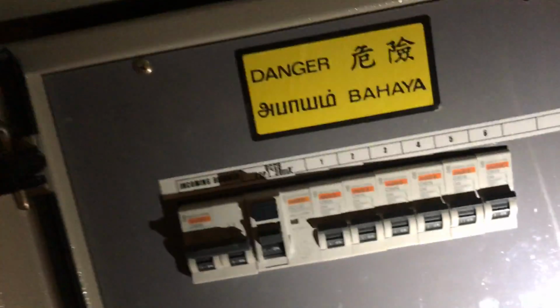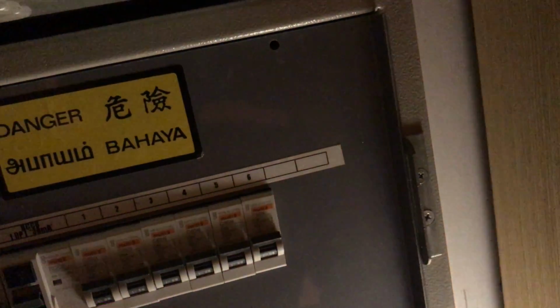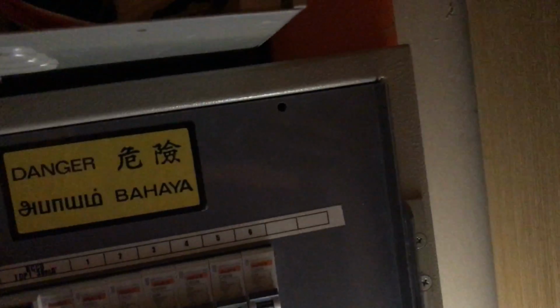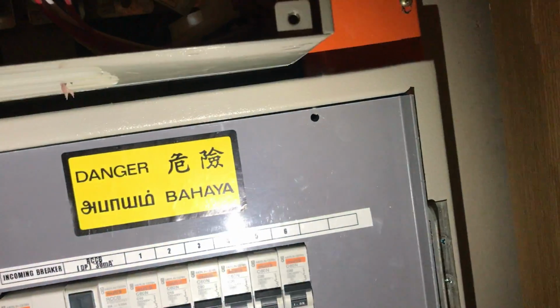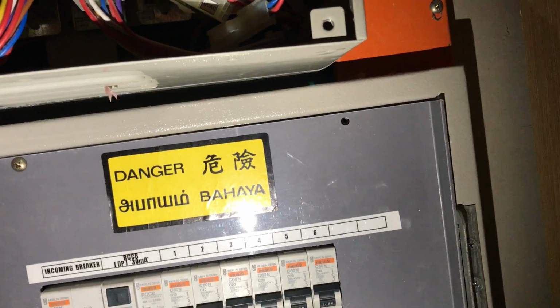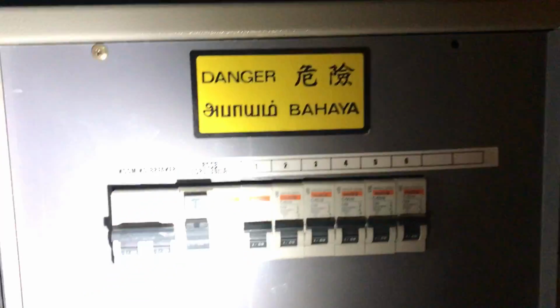Interesting, somehow there's 32 amps and the main is 40 amps. 40 multiplied by 220 is 8.8 kVA. Damn, that's high for a hotel room. But the incoming breaker looks good though.